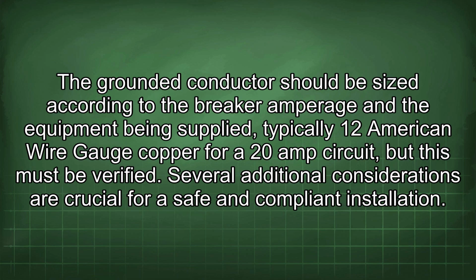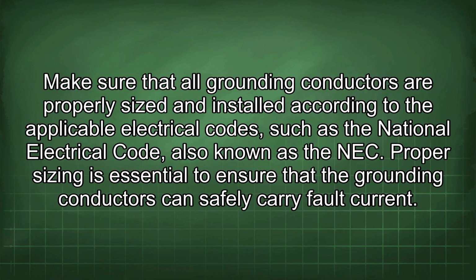Several additional considerations are crucial for a safe and compliant installation. Make sure that all grounding conductors are properly sized and installed according to the applicable electrical codes, such as the National Electrical Code, also known as the NEC. Proper sizing is essential to ensure that the grounding conductors can safely carry fault current.